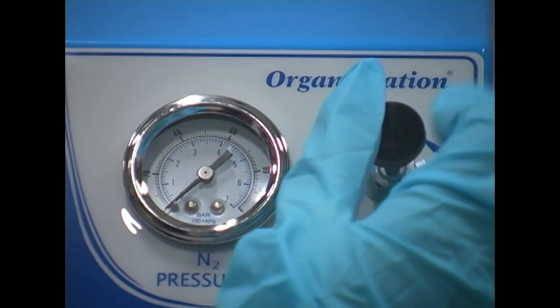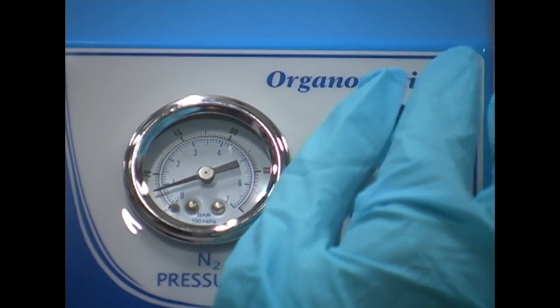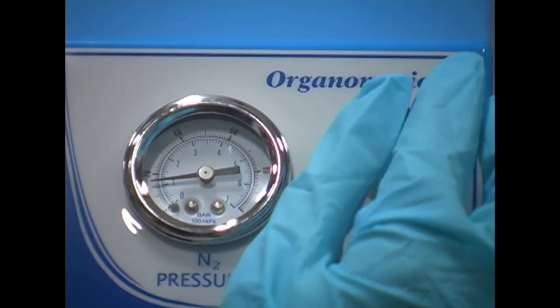The NitroGen uses a hollow fiber membrane to convert compressed air to a stream of 95 to 99% pure nitrogen gas.